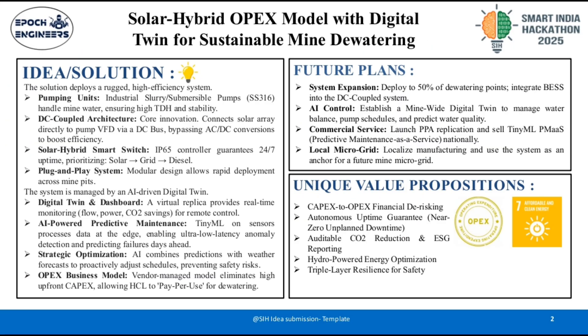Our solution is a three-part system built for ruggedness and efficiency. First, the hardware. We use industrial-grade slurry or submersible pumps made of SS316 to handle corrosive mine water and guarantee durability. The core innovation is our DC-coupled architecture connecting the solar array directly to the pump's VFD, which bypasses energy-wasting AC-DC conversions, drastically boosting efficiency.